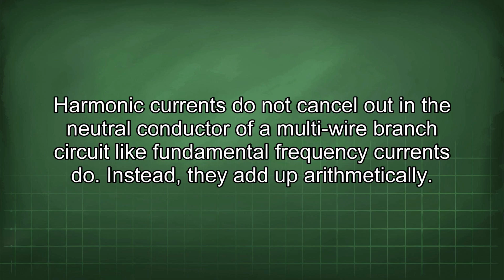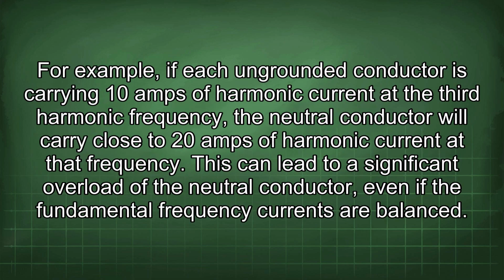Harmonic currents do not cancel out in the neutral conductor of a multi-wire branch circuit like fundamental frequency currents do. Instead, they add up arithmetically. For example, if each ungrounded conductor is carrying 10 amps of harmonic current at the third harmonic frequency, the neutral conductor will carry close to 20 amps of harmonic current at that frequency. This can lead to a significant overload of the neutral conductor, even if the fundamental frequency currents are balanced.